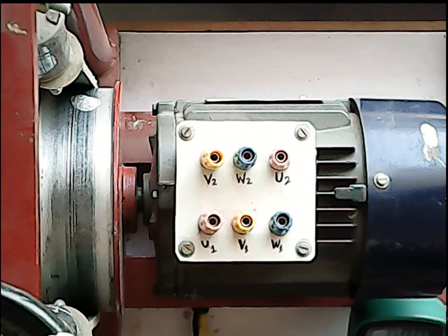As we know, in star configuration both the voltage and current values are less, and therefore during starting of an induction motor, star configuration is normally maintained for some time, so that the initial high surge of current cannot damage the windings of the motor. After that, the motor is automatically shifted to the delta configuration. Here we will not be going for an automatic changeover. The changeover we will do manually. However, in your next semester you will come across an automatic changeover circuit that you have to design by yourself.